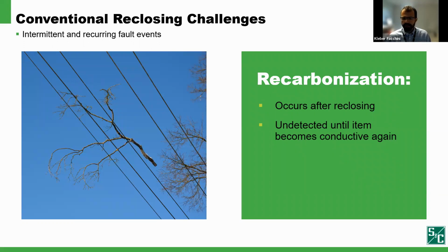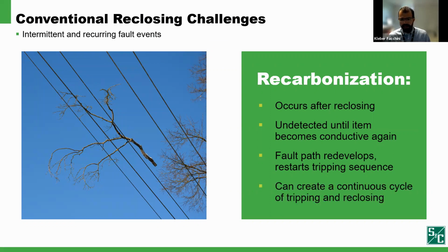Once the fault reinitiates and is detected, retripping of the fault interrupters occurs despite proper protection and fault interrupter operation. This happens because the conductive path of certain persistent faults is initially highly resistive and cannot be immediately detected upon reclosing. However, over time, the reapplication of rated system voltage across the fault path causes it to become less resistive. Once the fault path becomes sufficiently conductive, the fault is detectable and tripping is reinitiated. This can take tens of cycles or seconds, and if it takes a minute, repetitive fault testing sequences can occur.